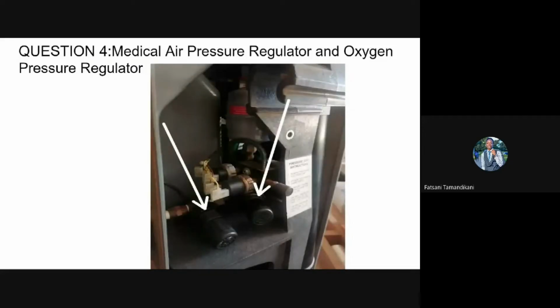You can adjust the delivery pressure using the pressure regulator that is attached to the product tank in an AirSafe 5-liter concentrator. To do that, you need to follow these steps. The first thing you have to do is to locate the pressure regulator in your oxygen concentrator. In most concentrators, including the AirSafe 5-liter, the pressure regulator is attached to the product tank, as you can see in the graphics. So in the graphics there, it's showing 2 pressure regulators. The first pressure regulator to your left is the medical air pressure regulator. That is the air that is coming directly from the compressor and purified air. So that is for regulating the pressure for that air.